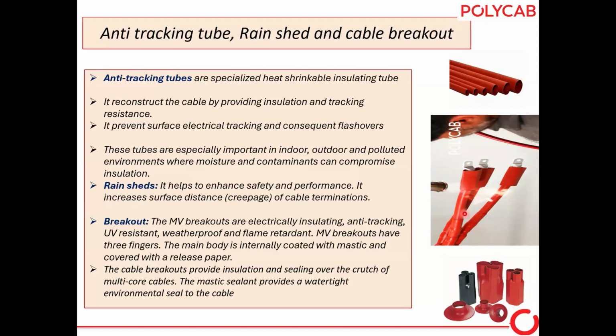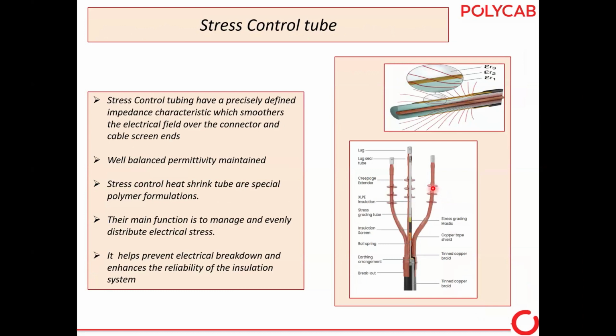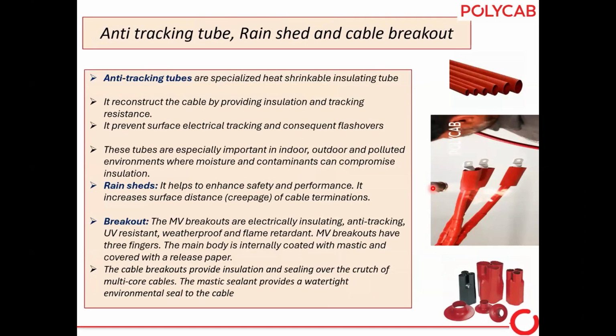These tubes have indoor and outdoor applications. These are the rain sheds. Rain sheds are used to enhance safety and performance. They increase the creepage distance of the cable termination. Generally, we use rain sheds for outdoor terminations. For indoor termination, we do not use rain sheds, but sometimes one or two are used if it is in moist conditions or coastal areas, where in the rainy season humidity in the transformer box is very high. So there are chances of phase to phase or phase to earth faults. At that time, for indoor termination, we use the rain shed.